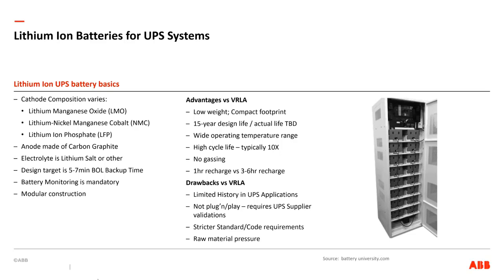They have very high cycle life, which may not be as interesting in a backup application like a UPS application, but the cycle life is typically 8 to 10 times what we see with a VRLA. So say a VRLA is designed to handle 300 cycles, a lithium-ion battery can typically be up around 3,000 cycles of cycle life. There's no gassing, at least in the normal mode. If they fail, there will be gassing.